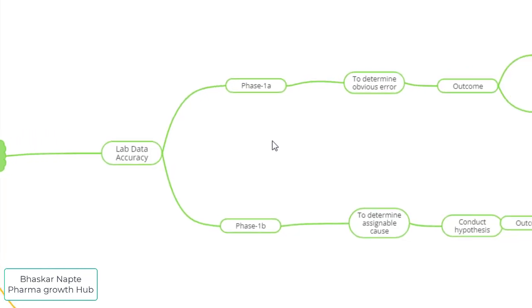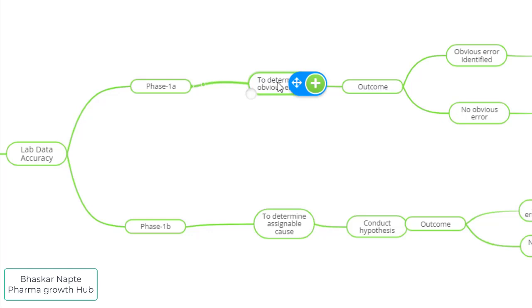Phase 1A is intended to determine if there is any obvious error associated with the reported OOS result. Obvious errors are those which have direct, detectable evidence — for example, wrong peak integration in chromatographic analysis, different instrument parameters in instrumental analysis, dilution errors, or weighing errors. These can be verified very easily because direct evidence is available. Phase 1A is designed to detect and identify such errors.